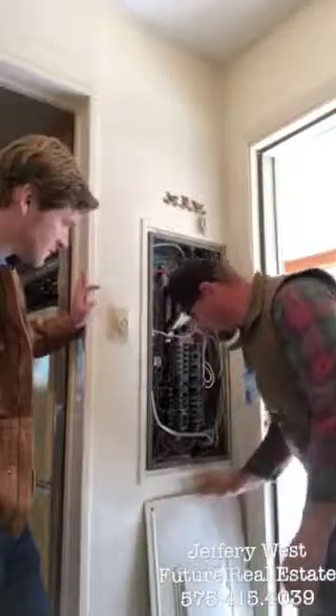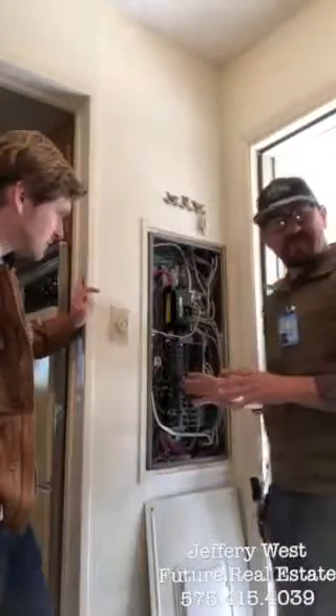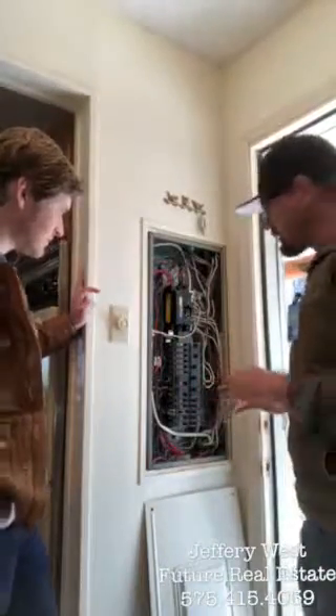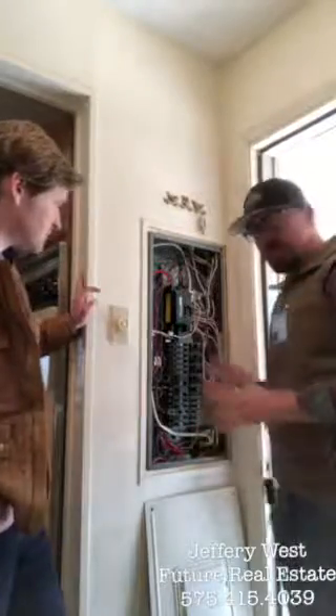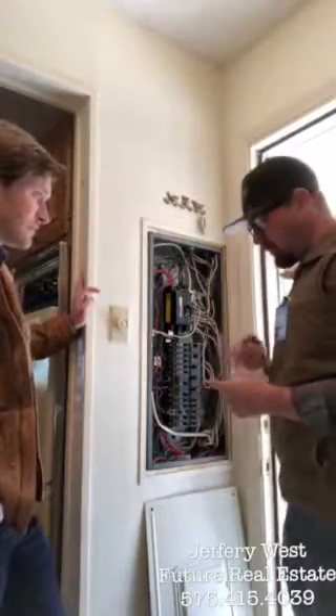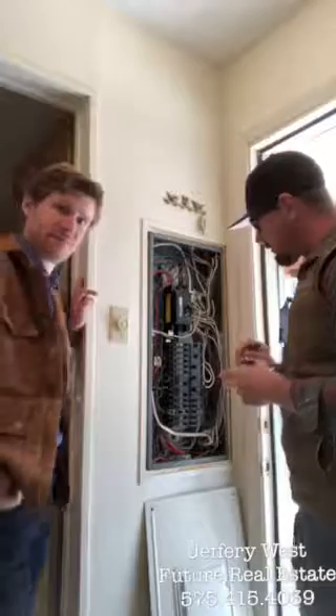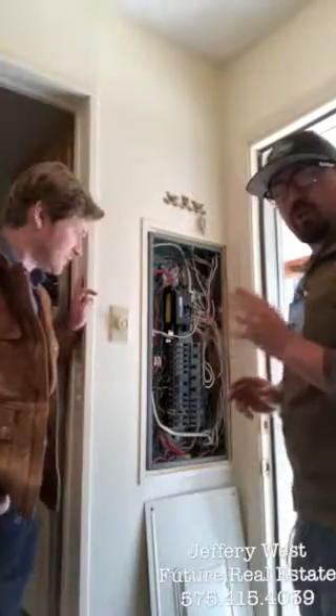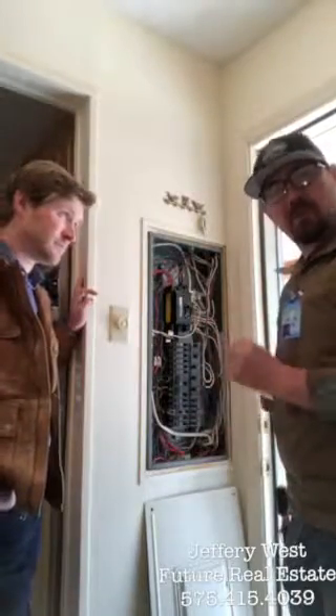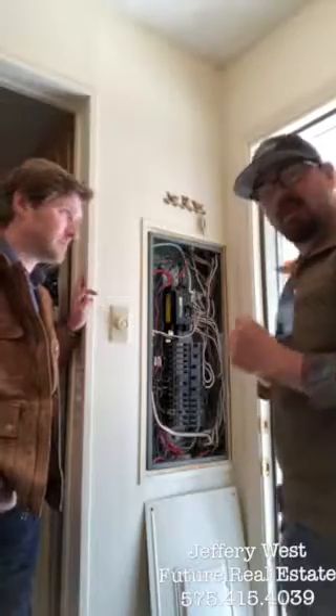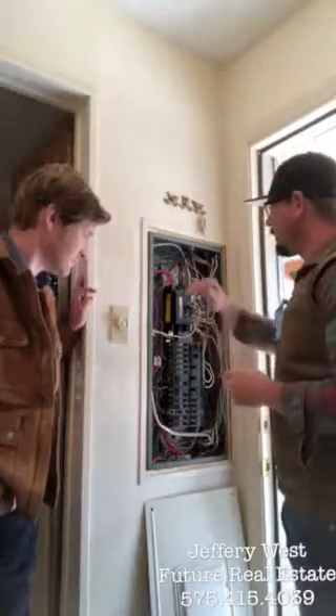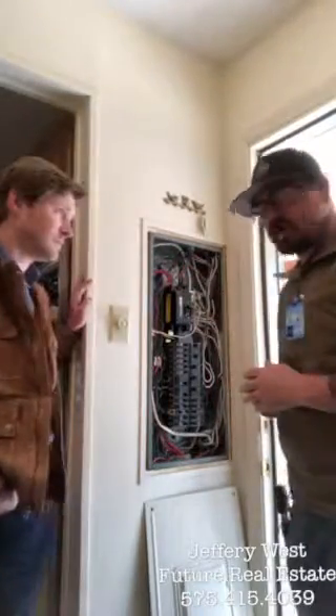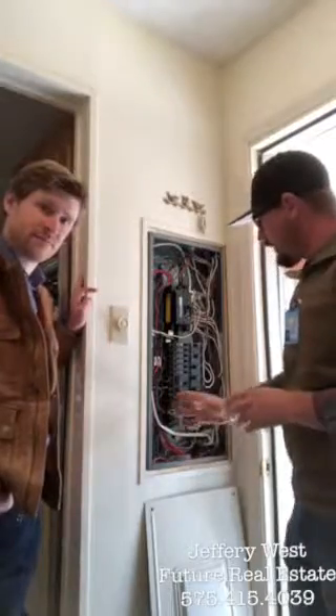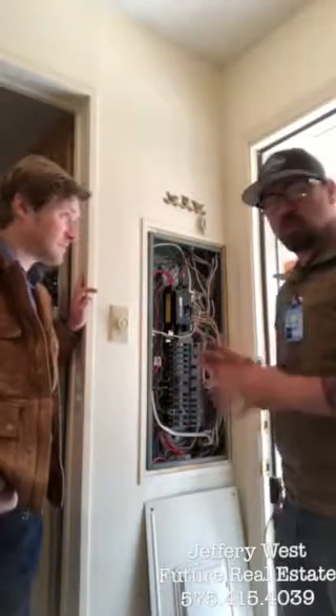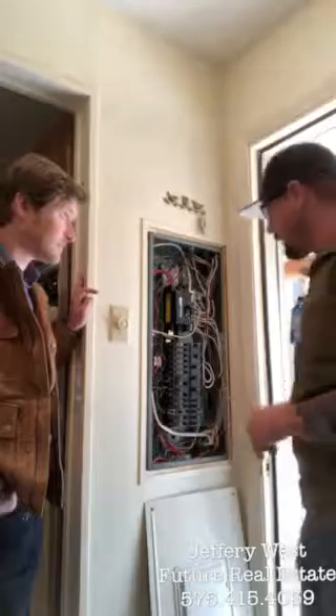It's a little messy in here, not as clean as some panels we normally see, but there are a few key factors we look for. We're gonna look for arcing, and for double taps, which is two or more wires going into a single breaker connection or underneath a single lug nut. We're also going to verify our main service into the structure, and make sure we don't have any loose wire connections inside this panel.